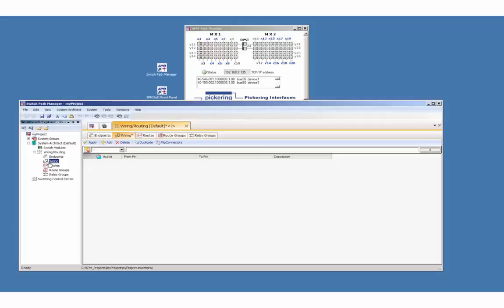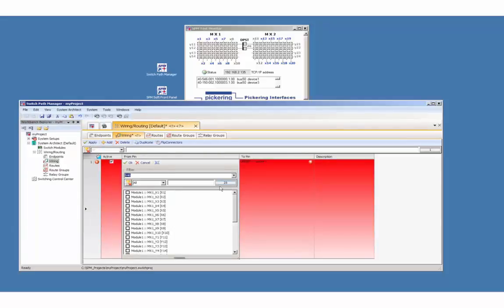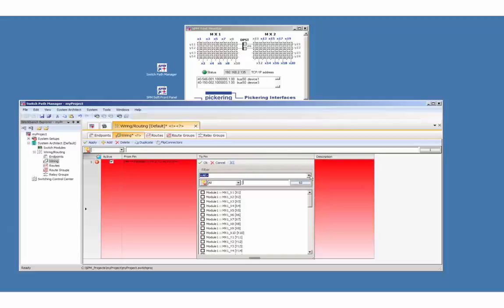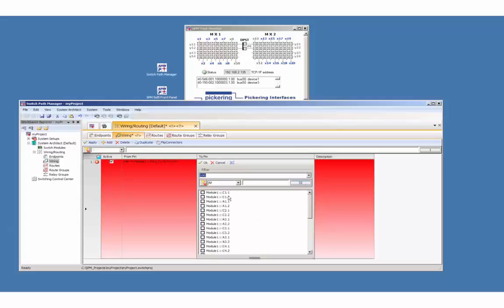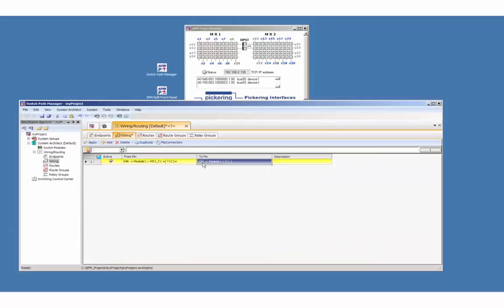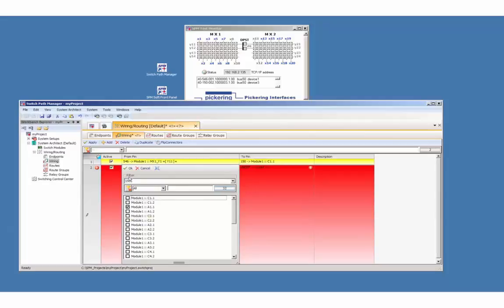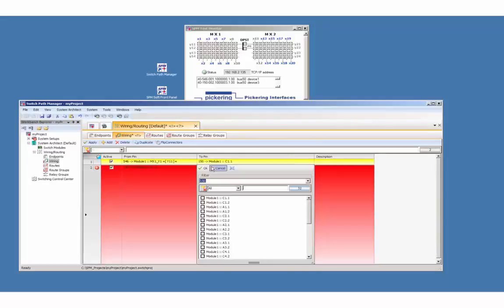Add a wire and define the from pin. Apply a display filter by selecting 546. Select Y1.1 and press ok. Now define where this wire should end. Define the to pin. Set a filter to 150 and select C1.1, which is the common of pole 1 of channel 1 of the double pole single throw relay card. Wire the other side of the relay by selecting 150A1.1 which goes to the 546Y2.1.